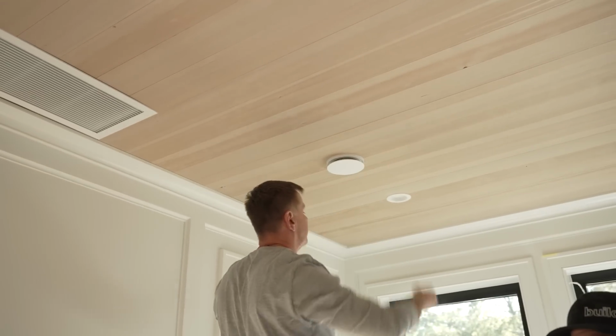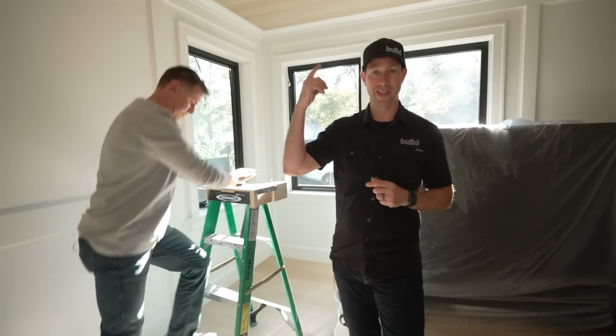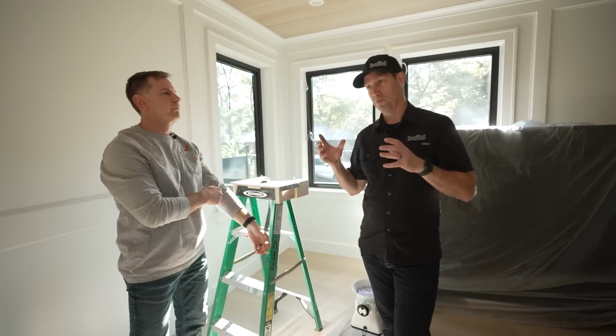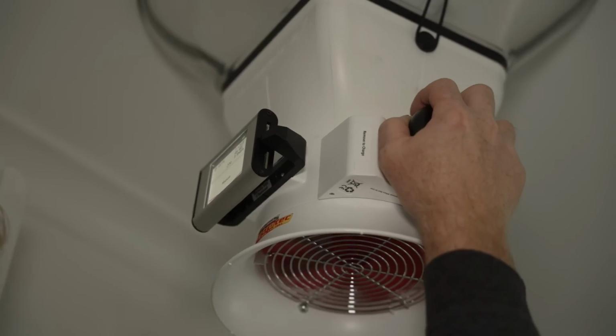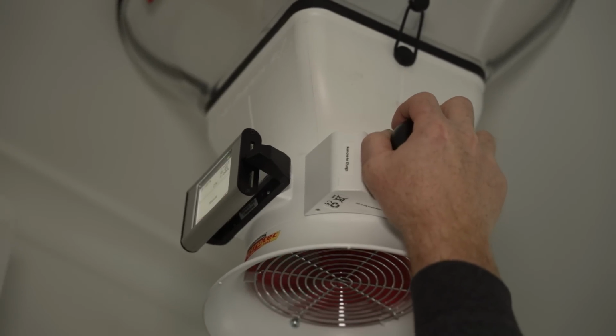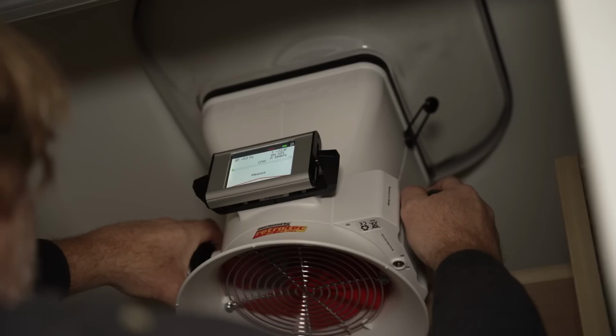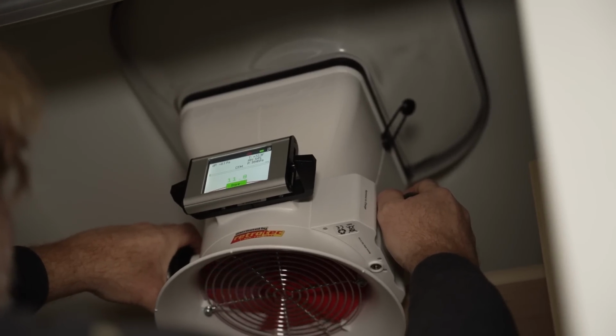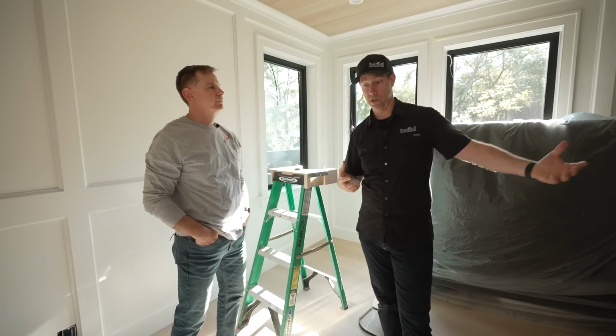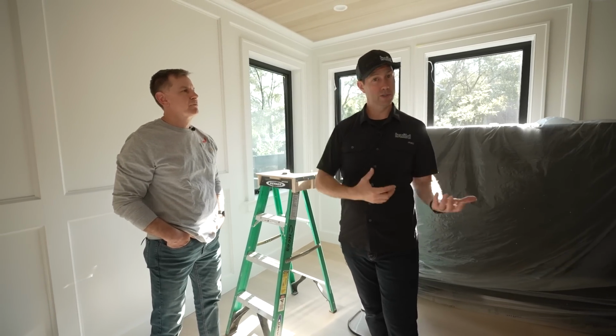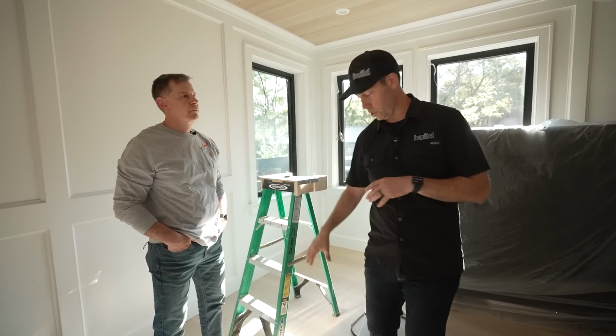When Gary got here this morning and fired up the machine in the attic, we went around with the flow hood checking each individual outlet, saying this one was designed for 36 CFM, this one's 36, because there's 2 occupants in this bedroom. So how many CFM do we get out, and if we need more, we can adjust it.